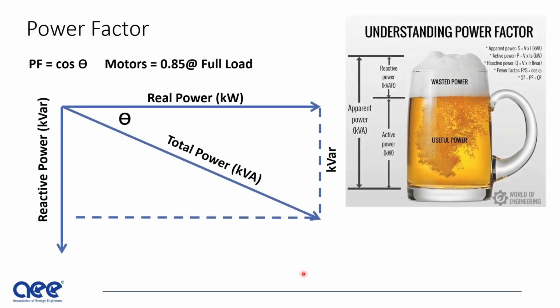Power factor, it's a big deal with motors. Lightly loaded motors generate a very poor power factor. I see over on the right here, I put this graphic. I think this is a ubiquitous presentation of power factor that I think is wrong. And I wish they would stop using it, because what they like to say is that this foam is wasted power. But this wasted foam, as they call it, is the reactive power.